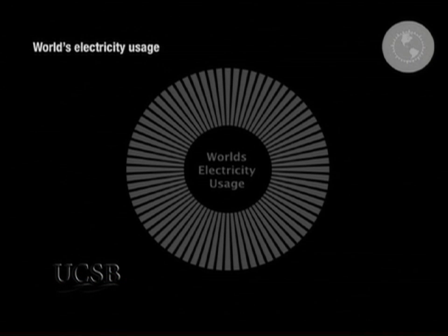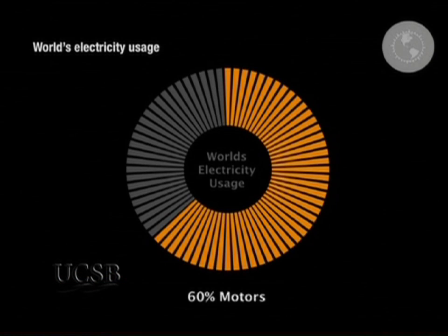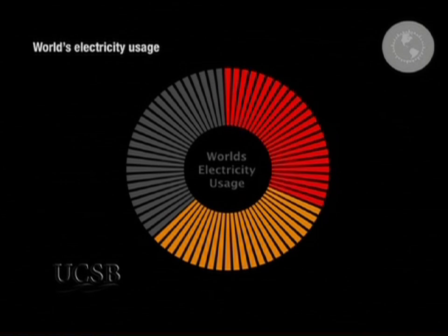Now, the same approach also works great in industry. For example, three-fifths of electricity runs motors, even a higher fraction in industry, and half of that electricity running motors is running pumps and fans on the other end of the motor. There are about 35 things you can do to retrofit a motor system with a 1-year payback to save about half the energy. The reason it's so cheap is of those 35 actions, 28 are free byproducts of the first 7.